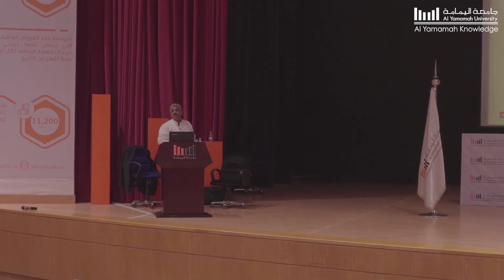with the right system. So what you see in red here is the product, and inside you see rock wool with special properties and specifications, where density is about 64 kilograms per cubic meter, and we talk about temperature resistance of almost 1,200 degrees under fire. So very high resistance. Again, in terms of designing, we talk about two things: fire rating and temperature rating.